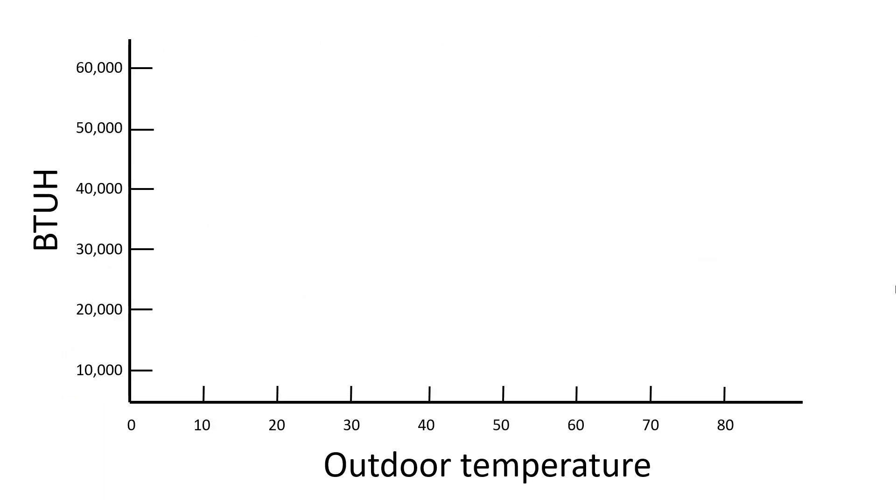In this video we're going to be talking about the heat pump balance point. The heat pump balance point is where the output of the heat pump equals the heat loss from the house.